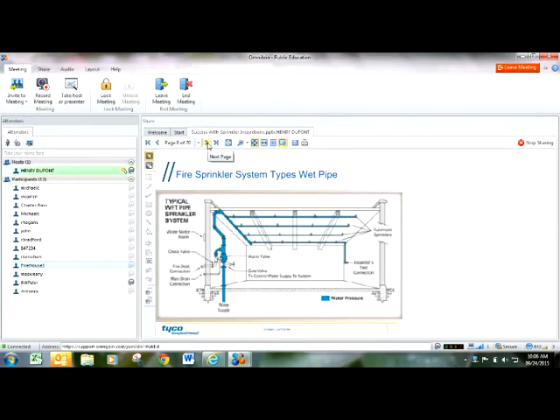So there's two main, very common types of sprinkler systems. The first most common sprinkler system is just a regular wet pipe sprinkler system. The major components of a wet pipe sprinkler system are the sprinkler heads, you see right there on the branch lines themselves, and the cross mains. This is the riser. That's what's referred to as a sprinkler riser. At the riser, you're going to have a main control valve, which is generally a backflow preventer. You've got a main drain, a way to drain the system.